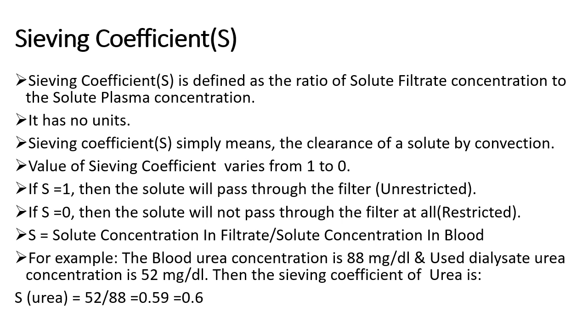Sieving coefficient represents the clearance of a solute by convection, and its value ranges from 0 to 1. If the sieving coefficient is 1, the solute passes through the filter unrestricted. If it is 0, the solute does not pass through at all — restricted transport. For example, if blood urea concentration is 88 mg/dL and dialysate urea concentration is 52 mg/dL, then S(urea) = 52 ÷ 88 = 0.59, or approximately 0.6. This means roughly 60% of urea is removed by convection.